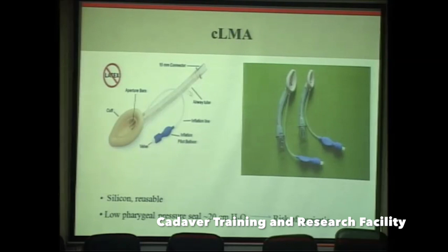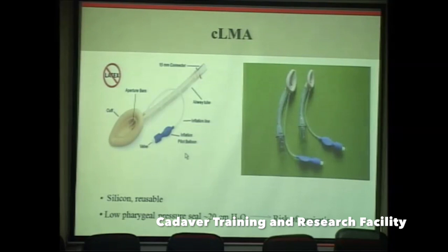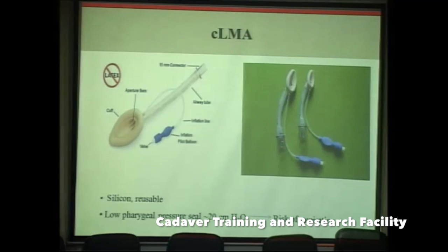The classic LMA is the benchmark for all laryngeal mask airways. Its different parts include the inflatable cuff, aperture bars, airway tube, a standard 15 mm connector, inflation line, inflation pilot balloon, and a metallic valve. It is made up of silicone and is reusable — the manufacturer recommends around 40 uses, but it is said it can be used over 100 times if properly autoclaved and maintained.